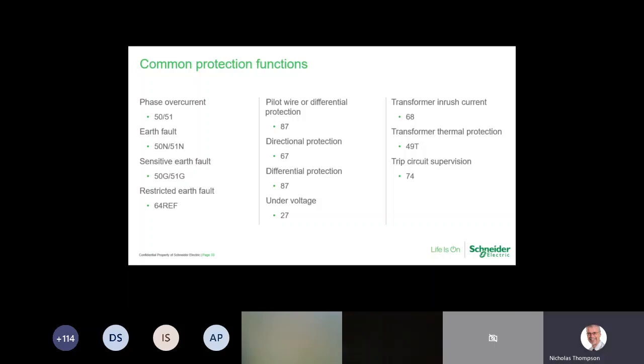Under voltage or over voltage, that's where you're looking for faults on voltage. So you might have a set point as plus 10% of your normal network voltage, or 50% below your network voltage. So it's where you're going to be protecting the network against sensitive equipment which will suffer from voltage.